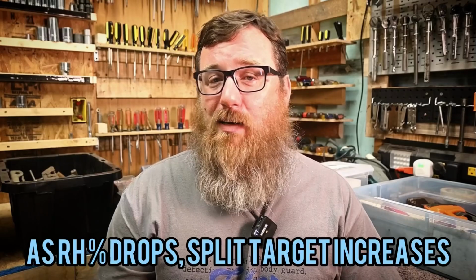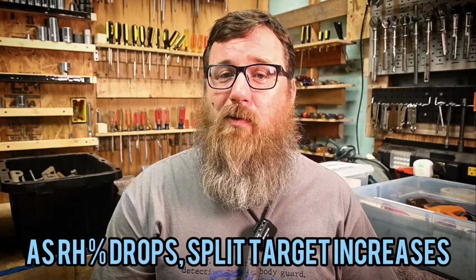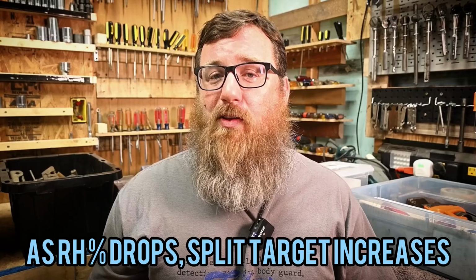Now keep in mind, if you get down to 50%, that's no longer acceptable. So you have to know where you're at so you know whether the split is good or bad. This is the issue I always had with home inspectors. When you're looking for a certain split, but they don't measure the relative humidity, then you really can't address what the actual split is. So if you see something that's way too low, like 12 or 13, they may think there's a problem with the system. But if the humidity is very high in the house, like the system's been off for a long time, and you live in a humid environment like the entire southeast United States right now, including where I'm at in North Carolina, it may really throw you off.